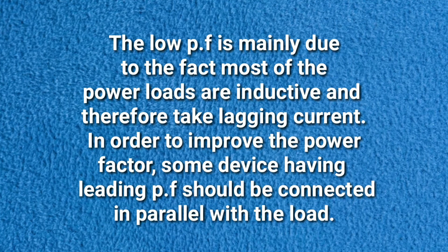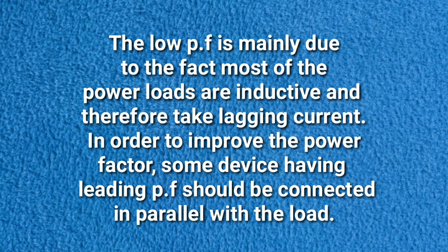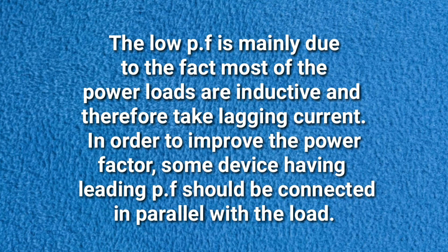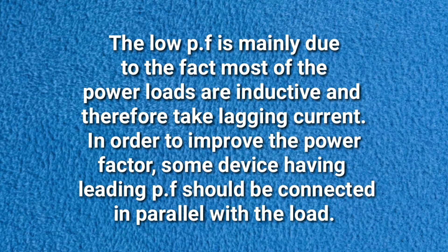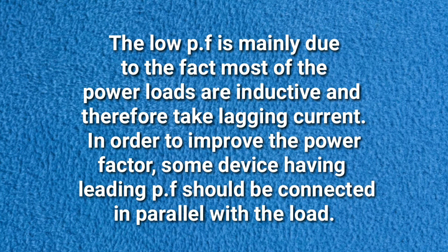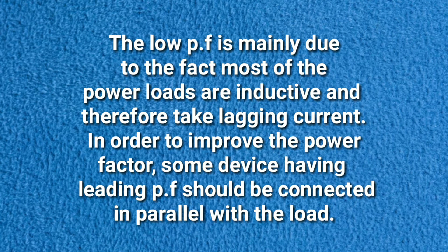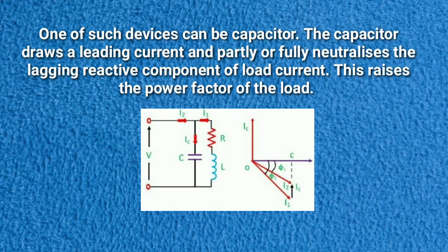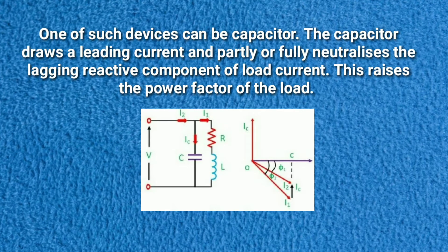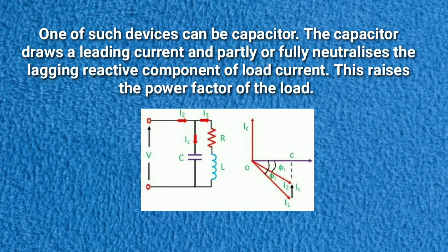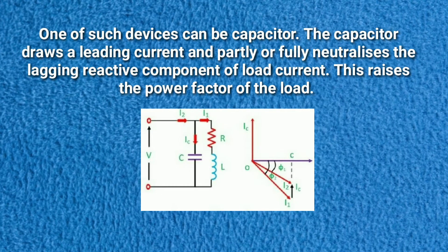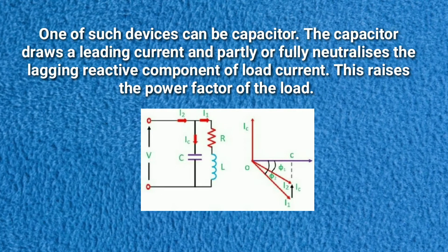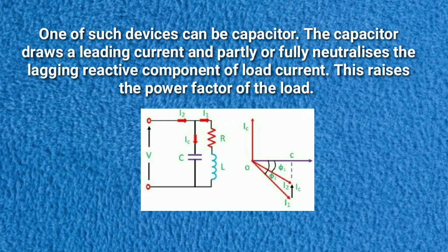The low power factor is mainly due to the fact that most of the power loads are inductive and therefore take lagging current. In order to improve the power factor, some device having leading power factor should be connected in parallel with the load. One such device can be a capacitor. The capacitor draws a leading current and partly or fully neutralizes the lagging reactive component of load current. This raises the power factor of the load.